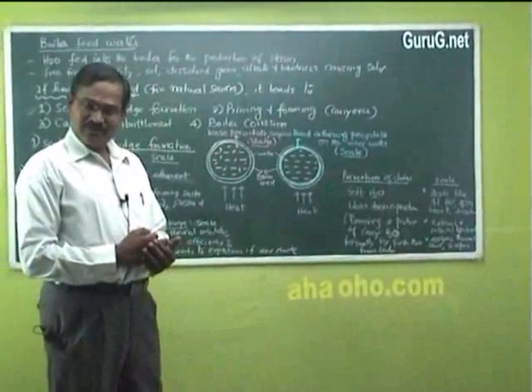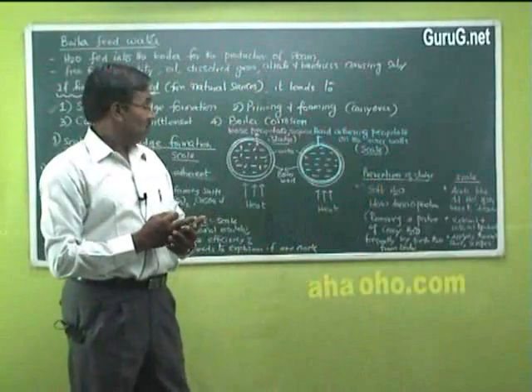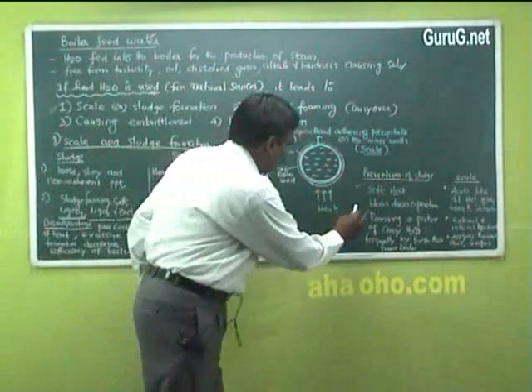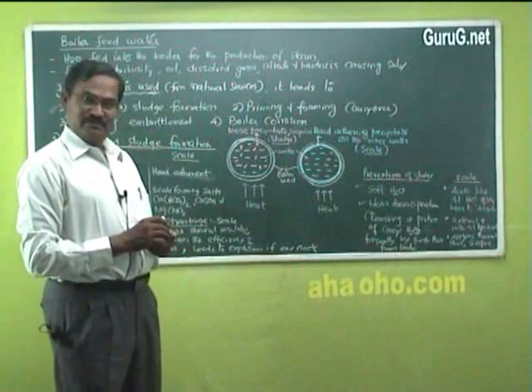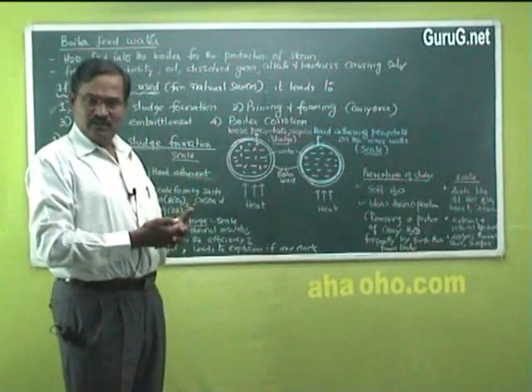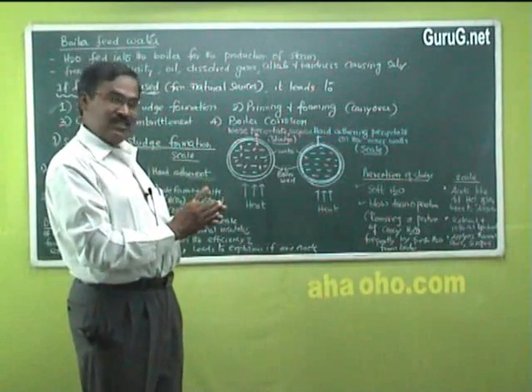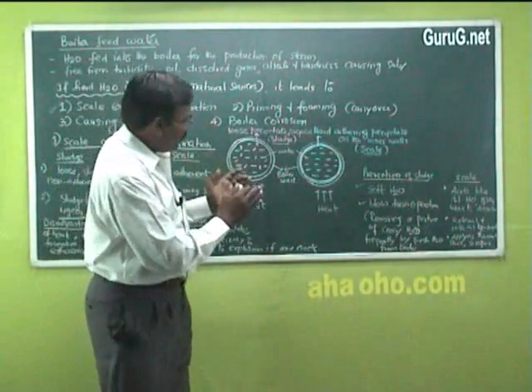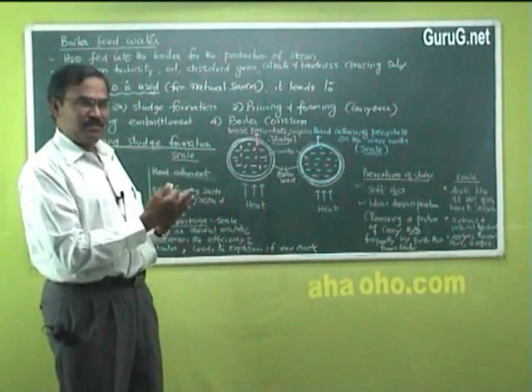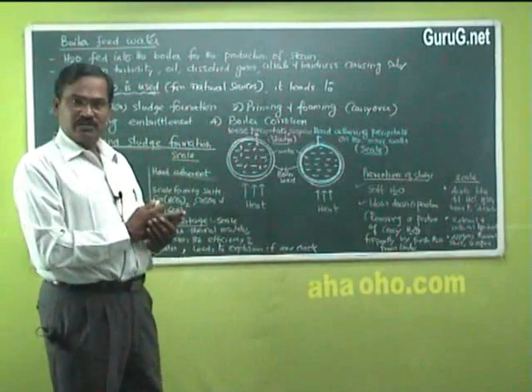These problems only occur when using hard water; soft water would avoid sludge formation. Since we cannot always use soft water, we go for remedial measures — the blowdown operation. When water boiling in the boiler becomes saturated with salts, a portion of that concentrated water is removed and replaced with fresh water, diluting it so the saturation point is avoided and sludge formation is prevented.